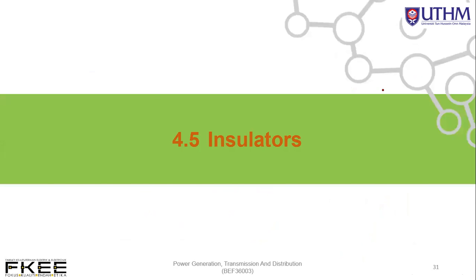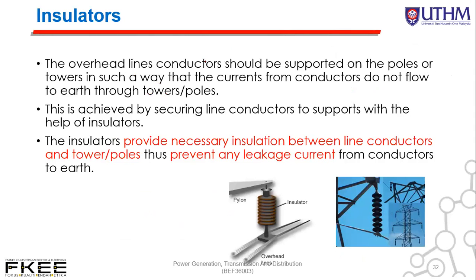Now kita tengok pada insulator. Insulator function dia adalah untuk insulate lah. Okay. The overhead line conductor should be supported on the poles or tower in such a way that the current from conductor does not flow to earth through tower pole. Okay. Kita ada tower, kemudian kita ada cross arm. So, jadi conductor yang nak bawa current tu kan dia mesti ada protection dia, iaitu gunakan insulator supaya current from the conductor tidak flow kepada tower. Okay, ataupun flow kepada cross arm tersebut. Okay, this is achieved by securing the line conductor to support with the help of insulator.